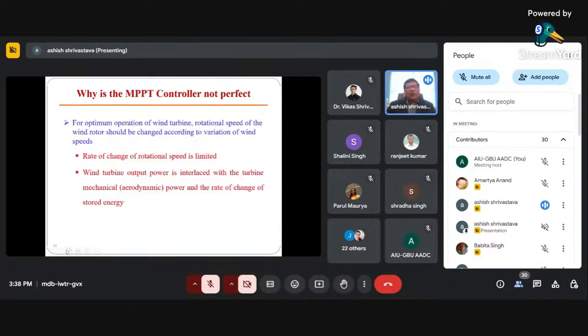So why is the MPPT controller not perfect? If you are not able to design a perfect MPPT controller, there could be a few reasons. One of the major reasons is that the rate of change of the rotational speed is limited. Then, the wind turbine output is interlaced with the wind mechanical or aerodynamic power and the rate of change of stored energy. If you are storing energy, and your rate of change of stored energy is changing, then it is also very difficult to design, because the controller should be given the data in the proper pattern.